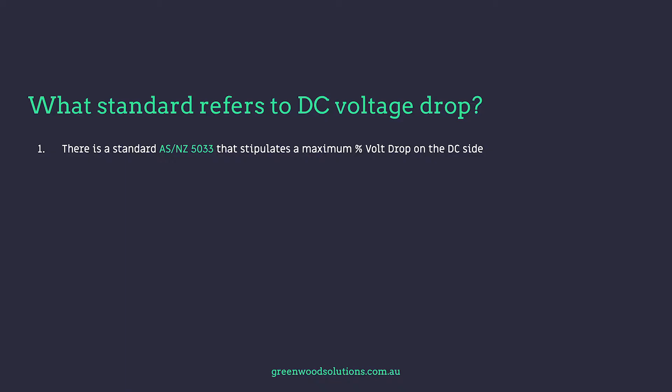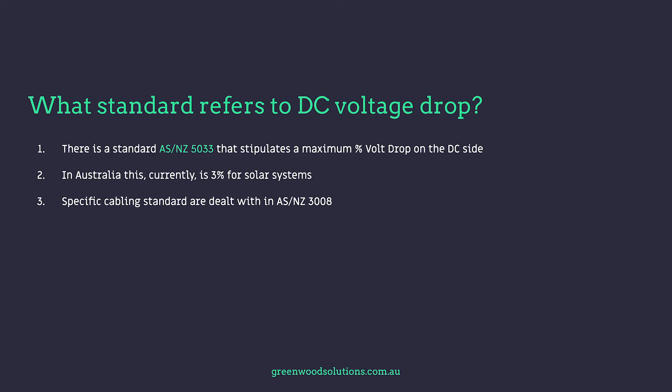So what standard do we reference when talking about DC Volt Drop? In Australia and New Zealand it is AS5033, and they stipulate a maximum Volt Drop percentage of 3%. For cable specs you must reference AS3008.